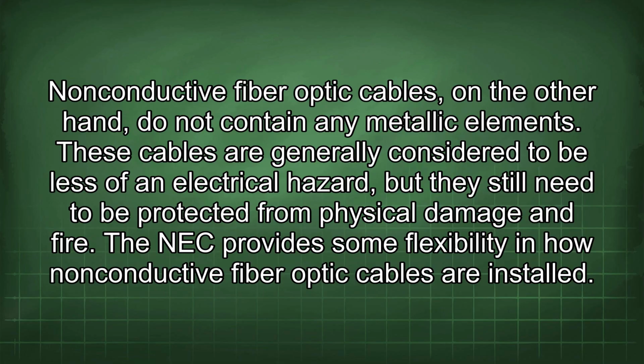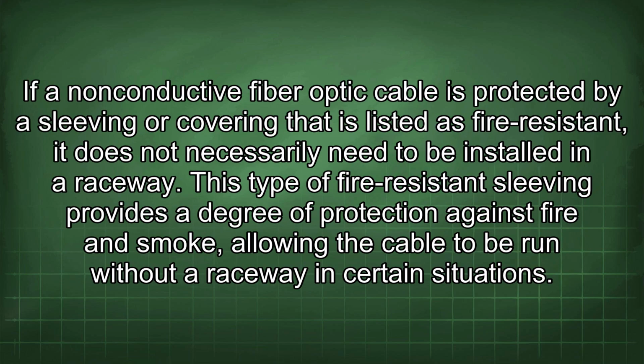Non-conductive fiber optic cables, on the other hand, do not contain any metallic elements. These cables are generally considered to be less of an electrical hazard, but they still need to be protected from physical damage and fire. The NEC provides some flexibility in how non-conductive fiber optic cables are installed. If a non-conductive fiber optic cable is protected by a sleeving or covering that is listed as fire resistant, it does not necessarily need to be installed in a raceway.